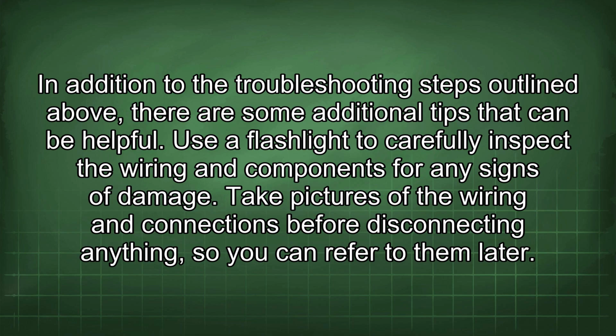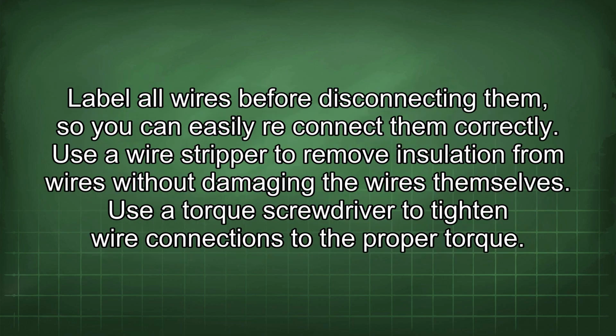In addition to the troubleshooting steps outlined above, there are some additional tips that can be helpful. Use a flashlight to carefully inspect the wiring and components for any signs of damage. Take pictures of the wiring and connections before disconnecting anything, so you can refer to them later. Label all wires before disconnecting them, so you can easily reconnect them correctly. Use a wire stripper to remove insulation from wires without damaging the wires themselves. Use a torque screwdriver to tighten wire connections to the proper torque.